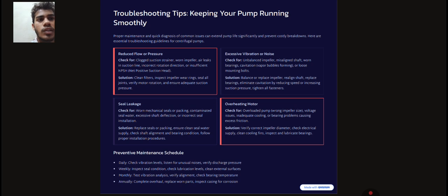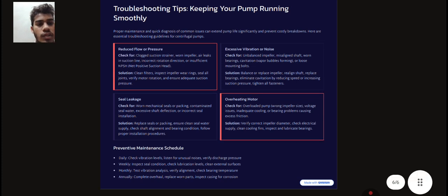Troubleshooting tips: keeping our pump running smoothly. Preventive maintenance schedule. Daily: check vibration levels. Listen for unusual noise. Verify discharge pressure. Weekly: inspect seal conditions. Check lubricant levels. Clean external surfaces. Monthly: test vibration analysis. Verify alignment. Check bearing temperature. Annually: complete overhaul. Replace worn parts. Inspect casing for corrosion.